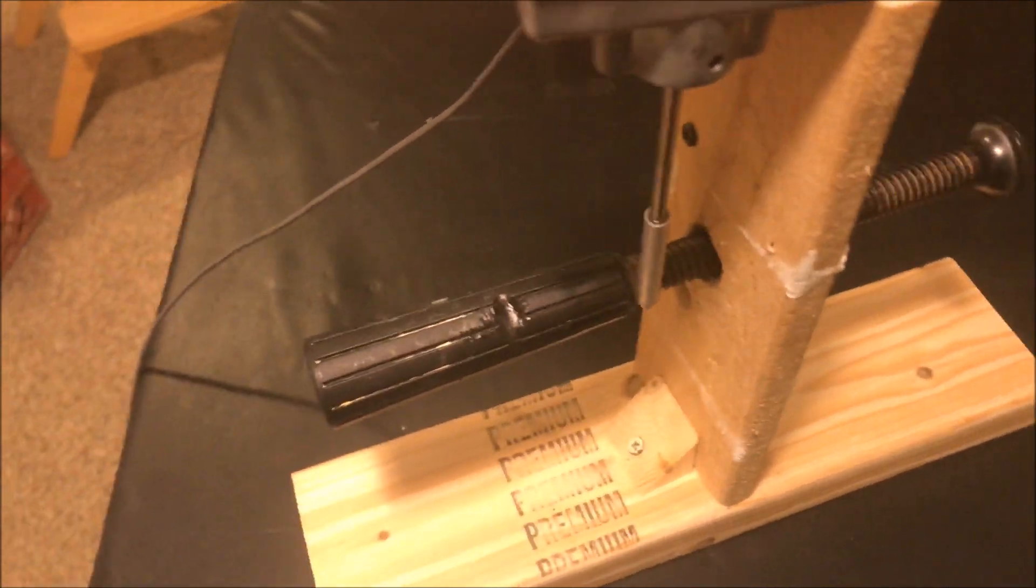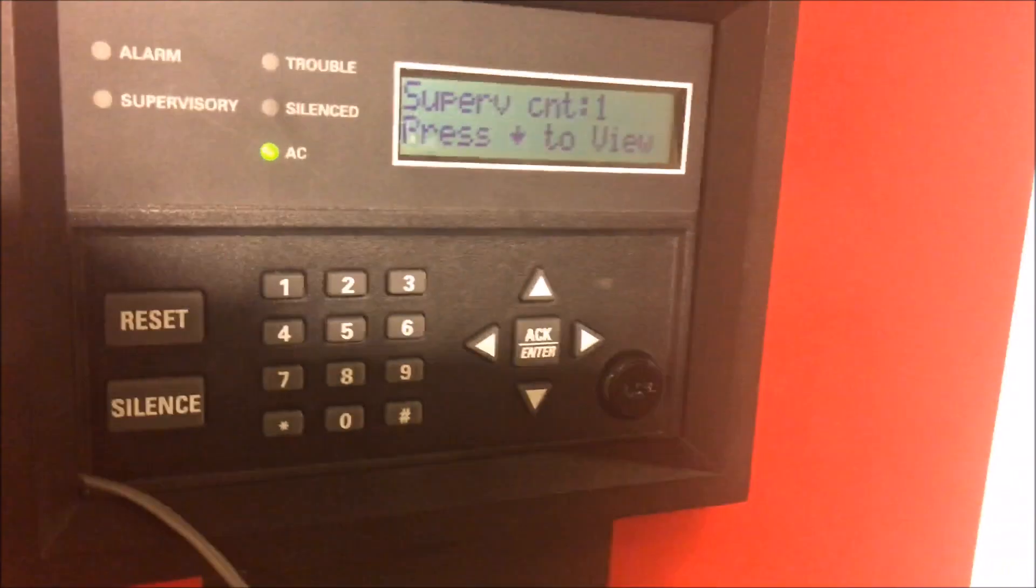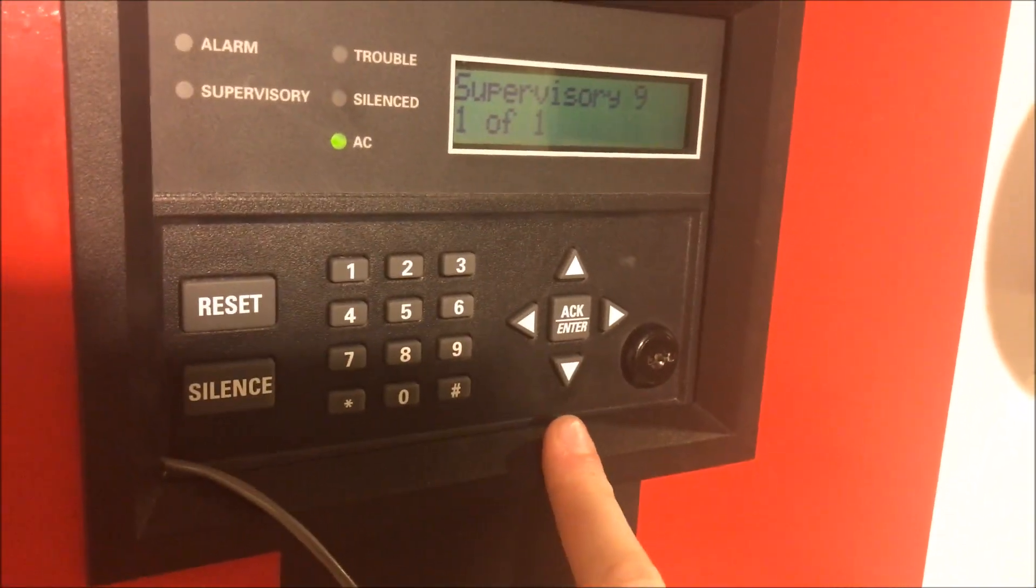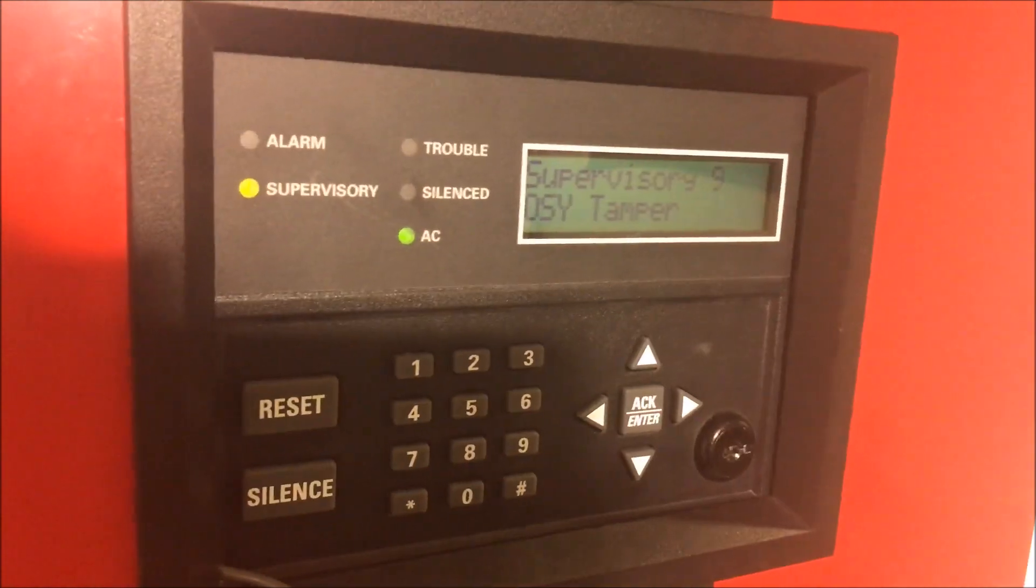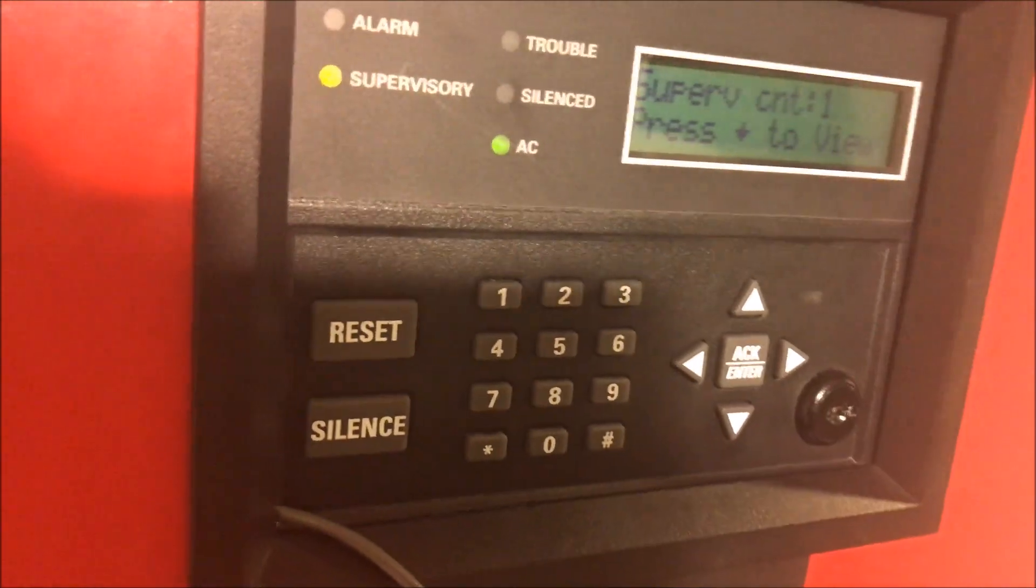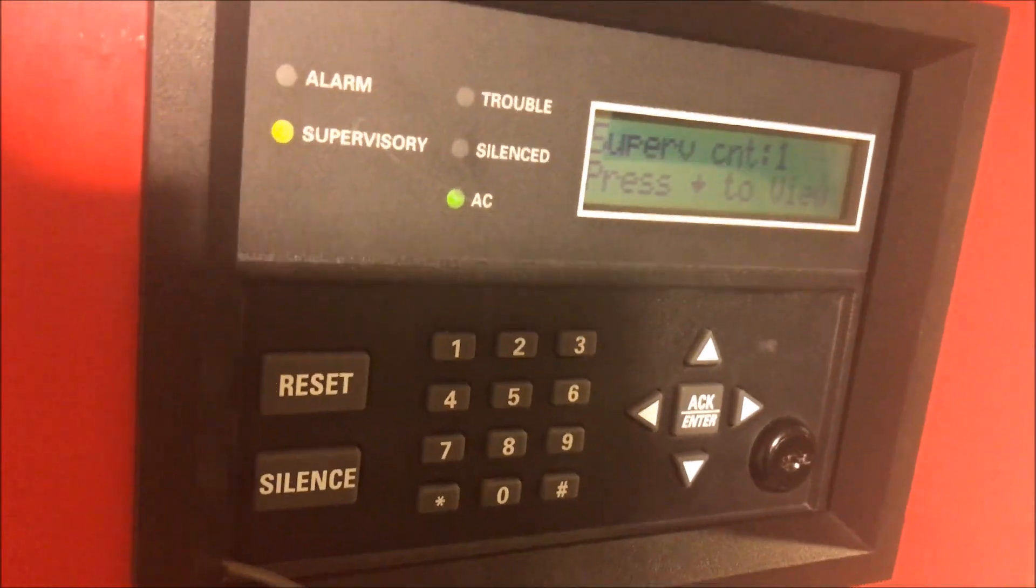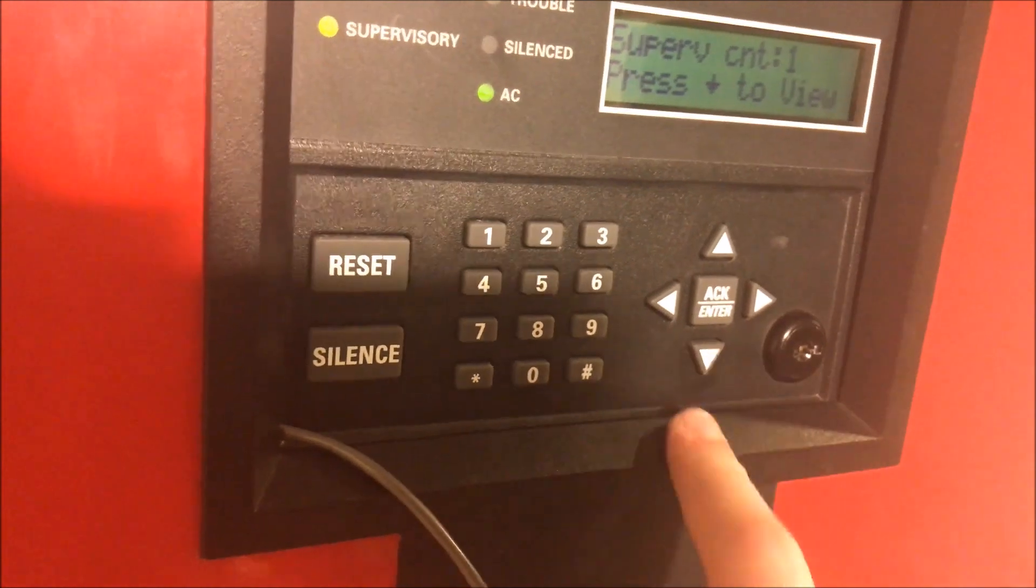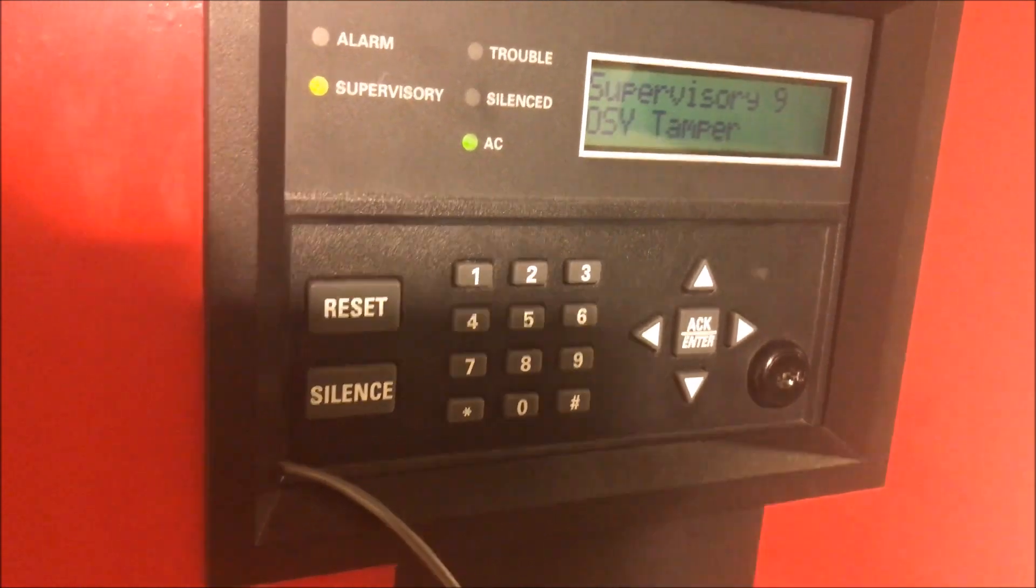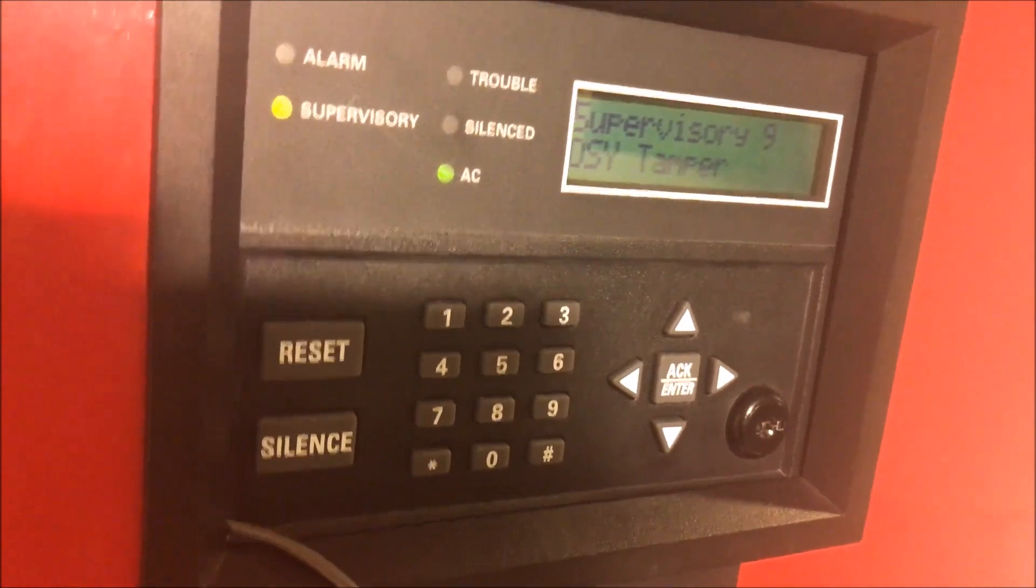And there, the panel goes into supervisory and if we come over to the panel, I am sorry about the lighting, I had to change it so you could see the switch. It says OS and Y tamper. That is my supervisory for the tamper switch. So OS and Y tamper.